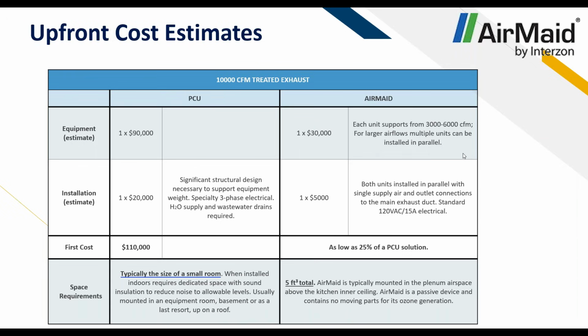And here's the first cost look. An estimated cost for a PCU is $90,000 to $100,000. Installation is another $20,000-ish. Now you're looking at about $110,000, $120,000, $130,000 for the first cost. And that's not even counting all the filters you're going to have to change 4 to 5 times annually. It's also very large, typically the size of a small room, and it's going to take up a large amount of roof space. With the AirMaid, we're looking at maybe $30,000 for a unit, $5,000 to install, and right there we're already at 25% less than a PCU solution. And it doesn't take up much room. You just need to install it above the plenum, or in the plenum, attached into the grease duct.